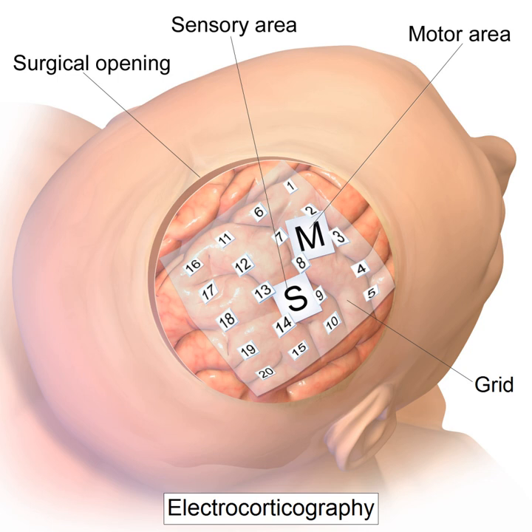Direct Cortical Electrical Stimulation, also known as cortical stimulation mapping, is frequently performed in concurrence with ECoG recording for functional mapping of the cortex and identification of critical cortical structures. When using a crown configuration, a handheld wand bipolar stimulator may be used at any location along the electrode array. However, when using a subdural strip, stimulation must be applied between pairs of adjacent electrodes due to the nonconductive material connecting the electrodes on the grid.